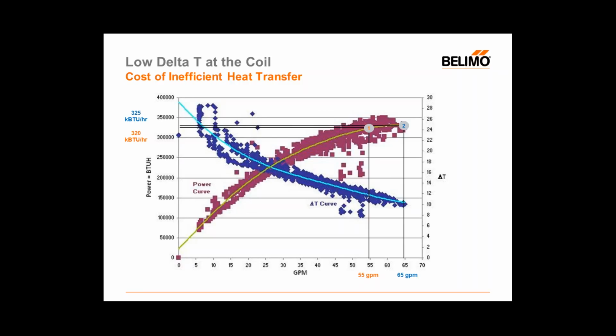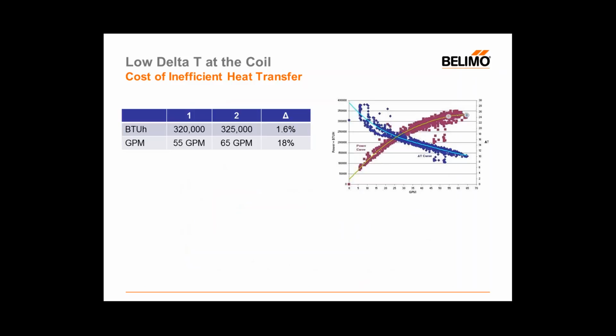And so the second point on there, point 2, is closer to 65 gallons a minute, so about 10 GPM more. And we only produce about another 5,000 BTUH. So we're going to say that that 5,000 BTUH is somewhat negligible, but we'll take a look at how this breaks down statistically and what we spent to achieve this more heat exchange. So basically, percentage-wise, we gained less than 2% more BTU by spending 18% more GPM to get there, which begs the question, how many dollars does it cost to pump 18% more water?